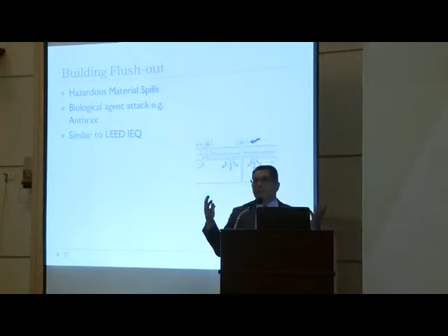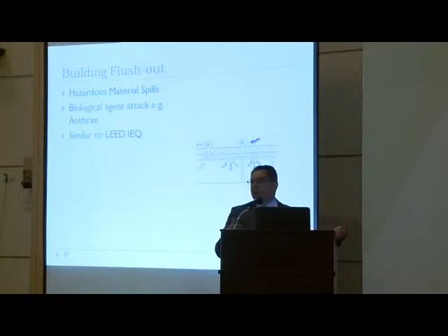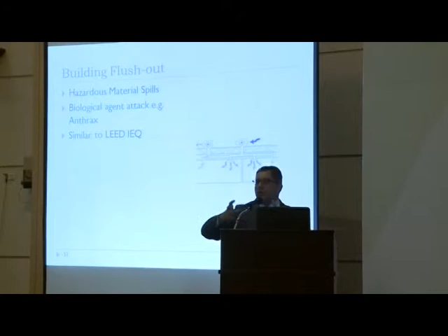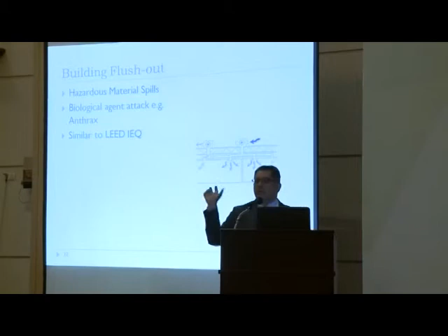Building flush outs. Suppose the emergency is actually internal. Someone comes up with anthrax and slams it on the floor, and you have a contaminated ward. Or someone comes into your emergency with SARS, and they're contaminated. What do you do? This is the ability to locate that area and flush out your system, so you don't want your biological agent circulating within the system. You just flush it out. All fresh air, everything goes out until your sensors tell you it's clear to go.